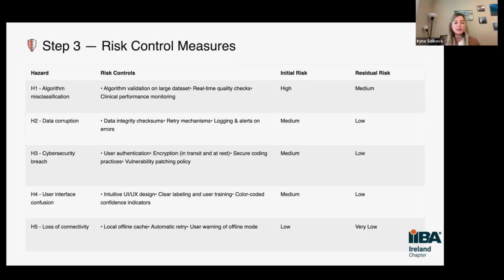For algorithm misclassification, what can we do? We can validate the algorithm on a large data set. We can do real-time quality checks and clinical performance monitoring. And we mitigate from initial risk high to residual risk medium. Then for hazard number 2, data corruption, we use data integrity checksums, retry mechanisms, and logging and alerts on error. This way we mitigate the initial risk from medium to residual risk low.